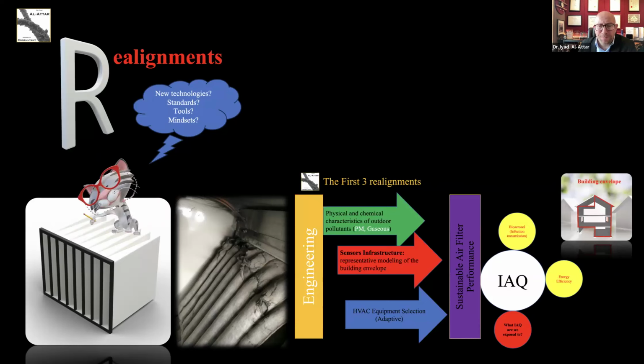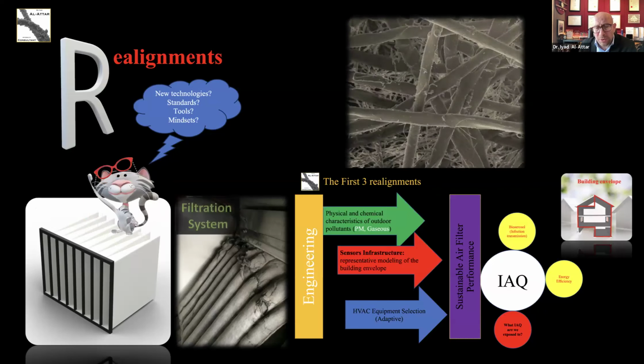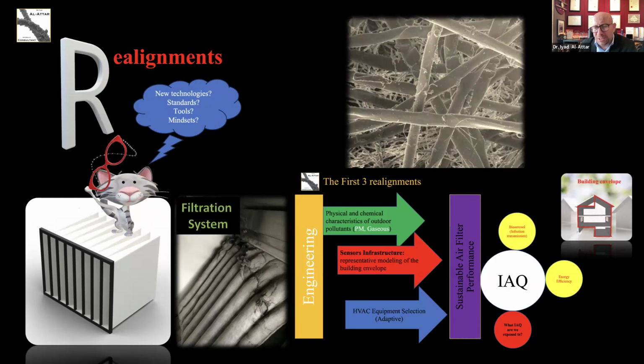You need an infrastructure of indoor and outdoor air quality monitoring, so you have mechanisms to determine how to respond to variations in indoor air quality relative to geographic location and the outdoor pollutants that challenge your system. Third is the HVAC equipment selection, which needs to be adaptive and responsive. Most importantly, think of filtration not only as a technology but as a system, so it can respond to any variation in indoor air quality.